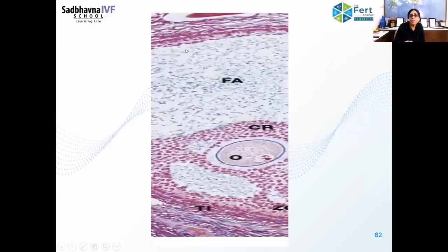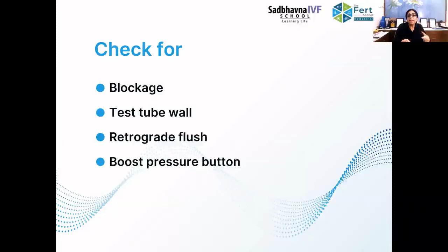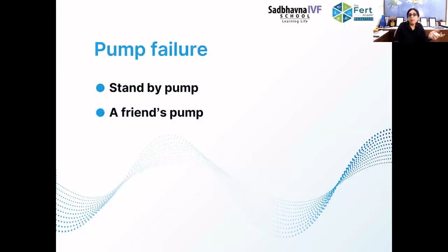Now, if the suction pressure doesn't build up, check for blockage, like when you're doing a null aspiration or in between. The test tube wall may be broken, or the cap may be broken. You do a retrograde flush, or you can use the boost pressure button. There's a red button which suddenly increases the pressure. Sometimes there's a clot in between, and then that gets cleared. Then what to do if the suction pump just stopped working? One thing is to have a standby pump. That is the best option. Or you have a friend who will give you a pump.